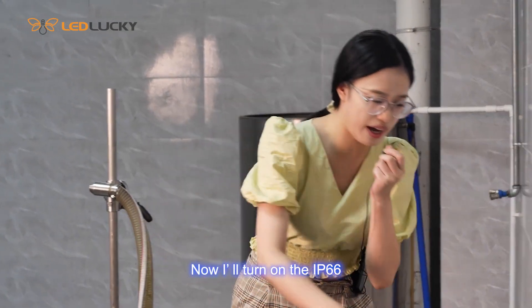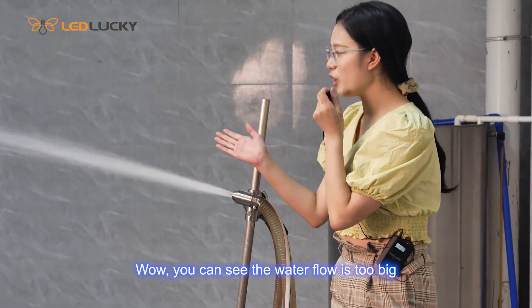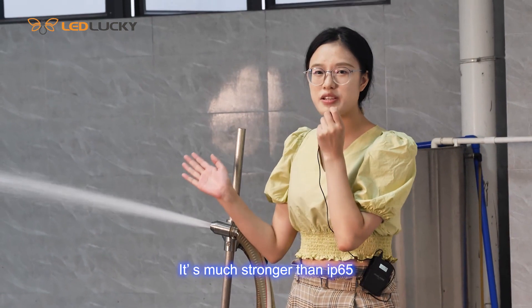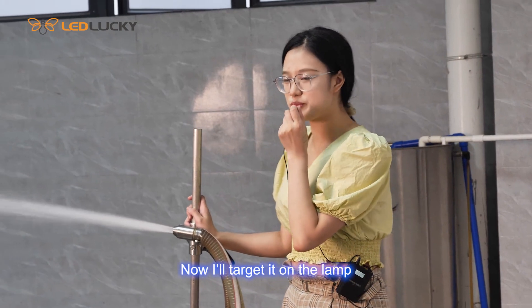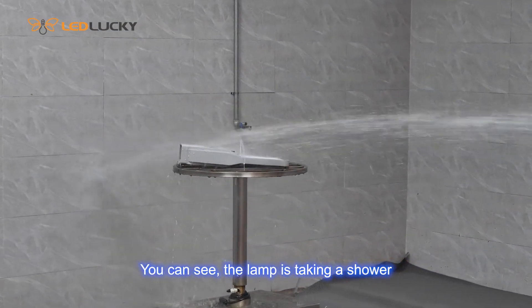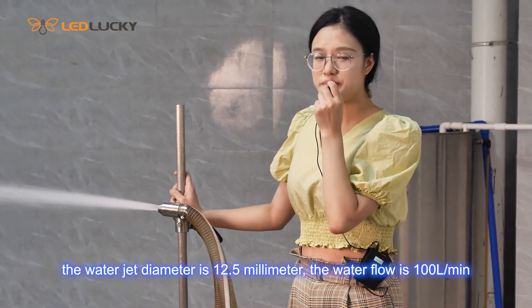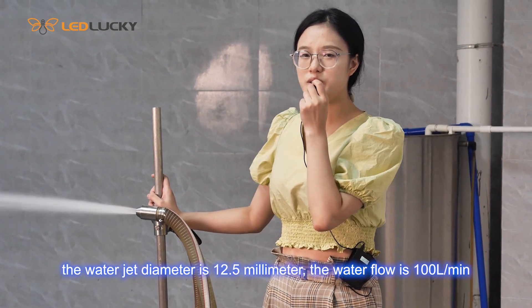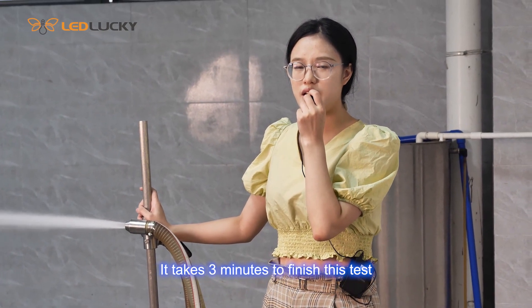Now I will turn on the IP66. Wow, you can see the water flow is much bigger — it is much stronger than the IP65. Now I will target it on the lamp. You can see the lamp is taking a shower. The water jet diameter of the IP66 is 12.5 millimeter, and the water flow is 100 liters per minute. It takes 3 minutes to finish this test.